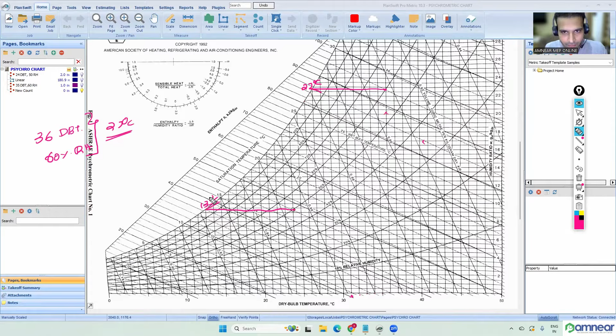There are four or five reasons. The first one, the condensation can come due to high humidity, meaning due to infiltration. If the duct or the condensate drain pipe has very poor insulation, then also this issue can come. If the duct components or duct fabrication is not proper, this issue can come due to duct leakage. And at the time of equipment selection, if the ADP, the apparatus dew point temperature of the cooling coil, is too low, or the supply temperature is low, meaning the off coil temperature at which the air leaves the machine, then also it can come.